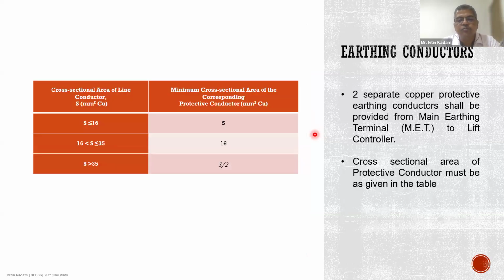Now, these values are also specified in the code documents. If the cross-sectional area of the line conductor is less than or equal to 16 square mm, you can have the same cross-sectional area for the protective conductor. If it is more than 16 square mm but less than or equal to 35 square mm, you can use an earthing conductor of 16 square mm. But if it is more than 35 square mm, you can take a value of S by 2.